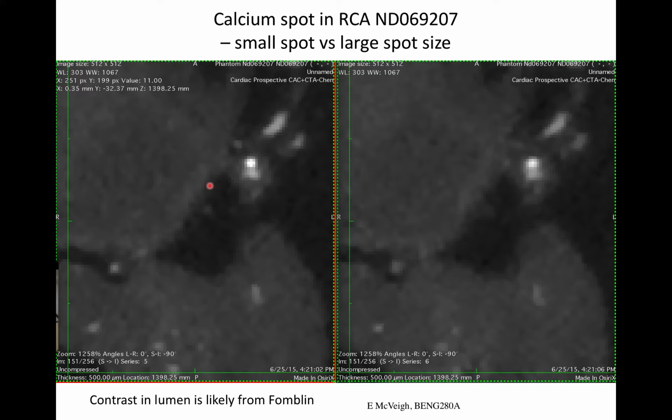And that happened around 400 mA. So at 399 mA, it was saying, I can do that with a 1 millimeter spot size. At 400 mA, it said, I need 1.5 millimeters. Right? So it opens up the spot size on the target to generate more X-rays, right? So without burning the target out, right?